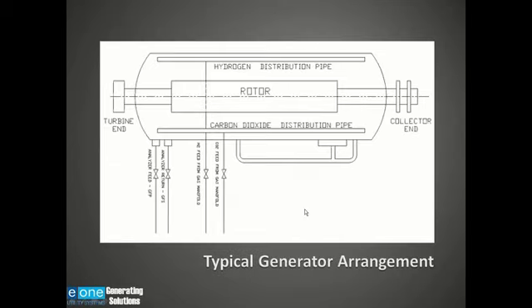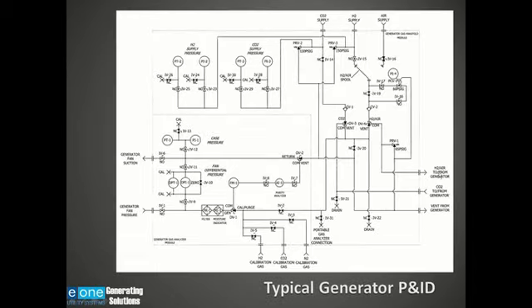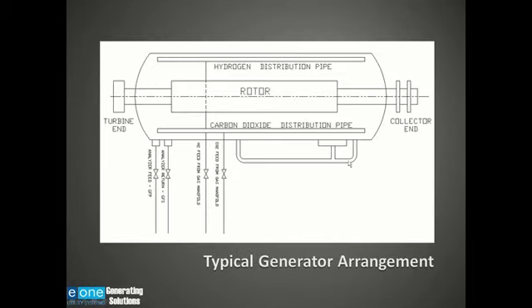Here's a section view again of a generator, and I just wanted to show this to point out that I've got the carbon dioxide distribution pipe or header that's located at the bottom of the generator. I have a hydrogen distribution pipe or header at the top of the generator. These two lines here are these right here. When I start a generator, I normally will have air in the generator when I'm coming offline or when I've done some work on the generator. So I need to get that air out of the generator so that I am not mixing hydrogen in air and creating an explosive mixture.